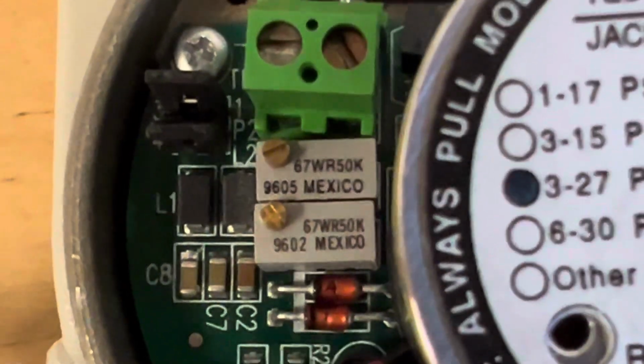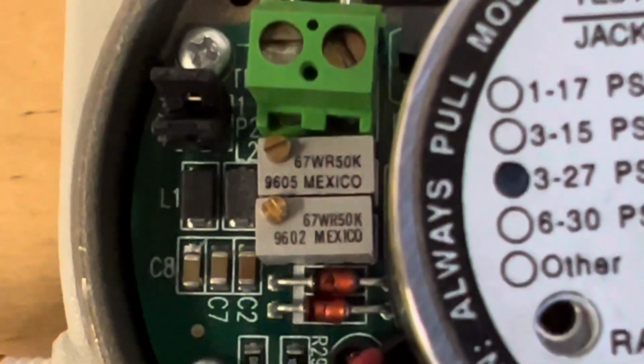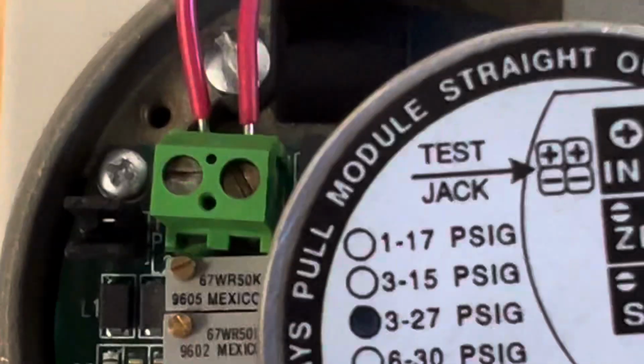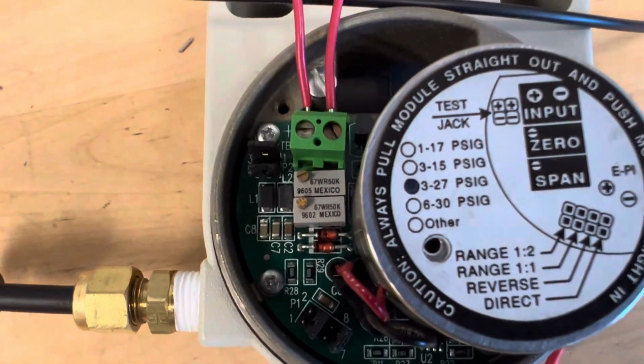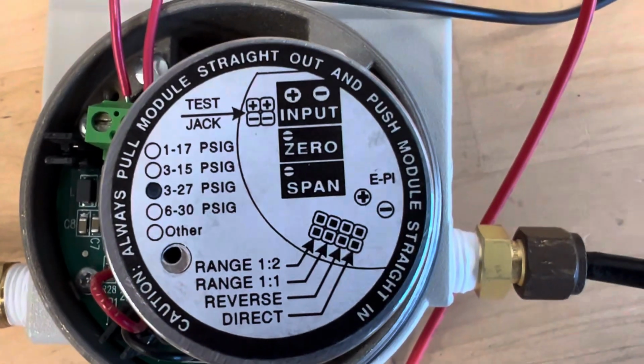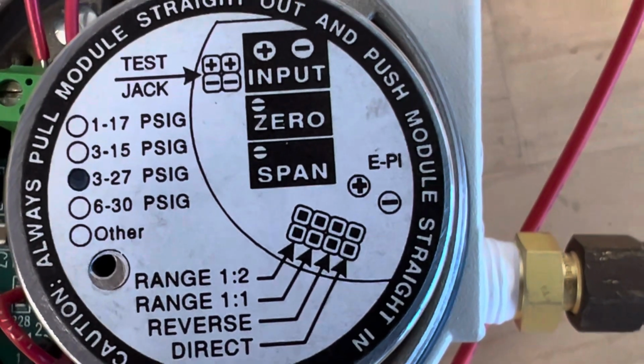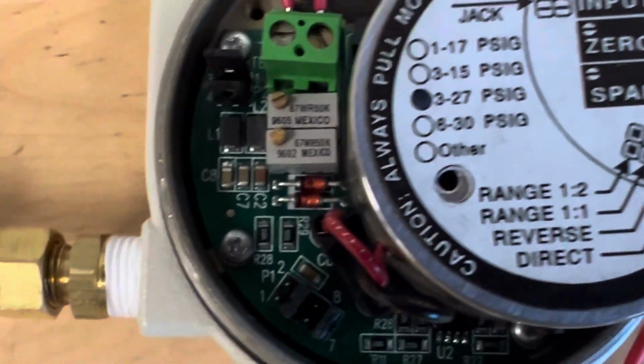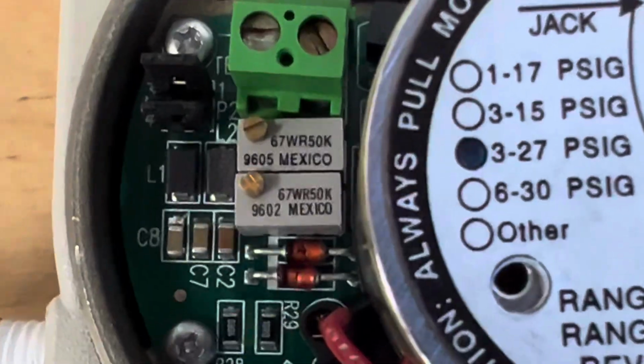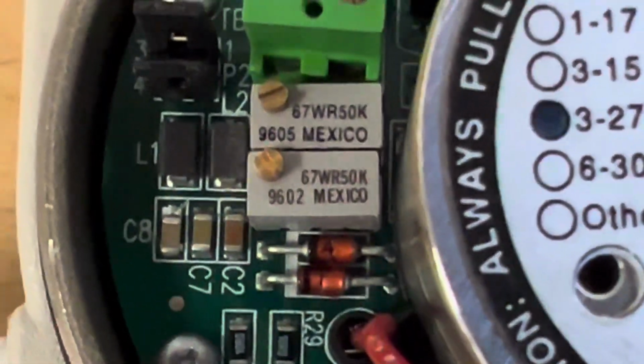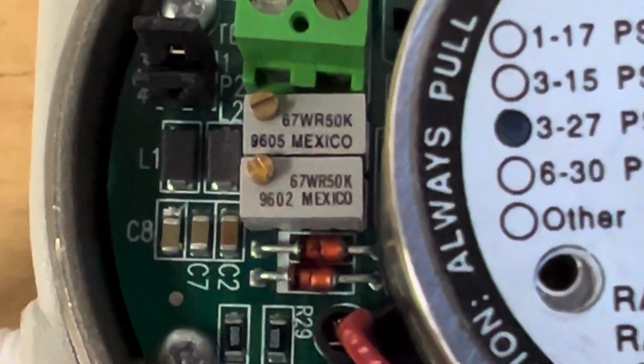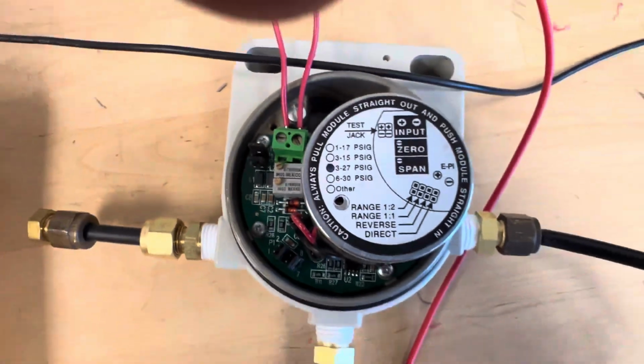That's how we're going to calibrate to our zero, which will be 3 PSI. Then we're going to adjust our span, and our span is going to be 15 PSI. And that's the lower potentiometer there, the little gray box.